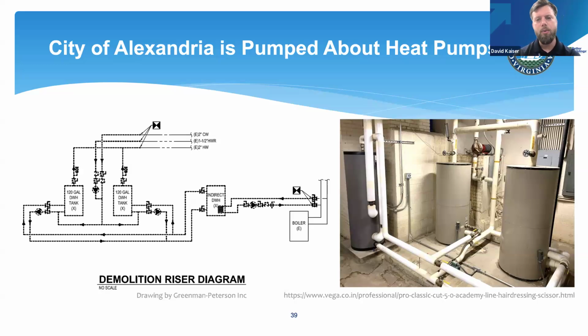But when you have a boiler system feeding a relatively large facility, mechanical engineers at the time were like, well, you've got a heating source already. Let's just reuse the heating source you have and put domestic hot water on it. The problem is that now you've obligated your space heating boiler to provide your domestic hot water heating energy all year round. So next, please.